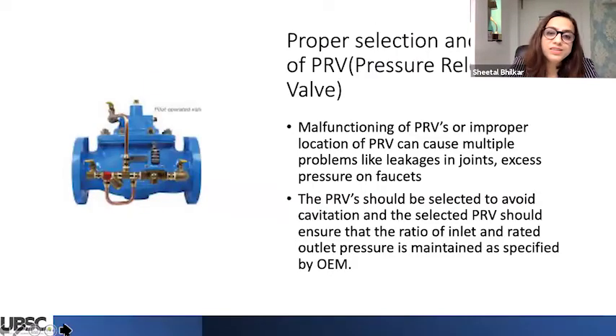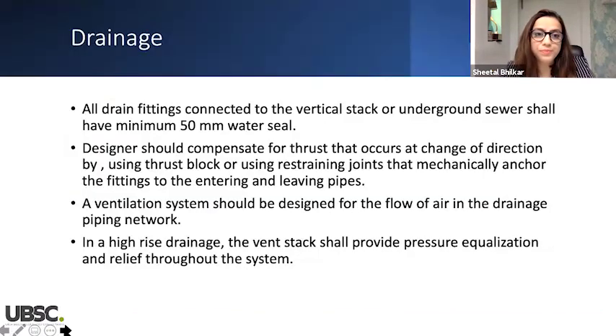Then you have to select these PRVs, pressure release valves, properly, because malfunctioning of these PRVs or improper location of the PRV can cause multiple problems like leakages in joints and even excess pressure. So PRVs should be selected to avoid cavitation, and the selected PRV should ensure that the ratio of inlet and rated outlet pressure is maintained as specified by the OEM.